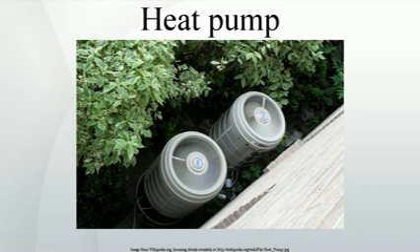Air-water heat pumps are otherwise similar to air heat pumps, but they transfer the extracted heat into a heating circuit, floor heating being the most efficient, and they can also transfer heat into a domestic hot water tank, and this water is consequently used in the shower and hot water taps of the building. However, groundwater heat pumps are more efficient than air-water heat pumps, and therefore the former is most often the better choice for providing heat for the floor heating and domestic hot water systems.